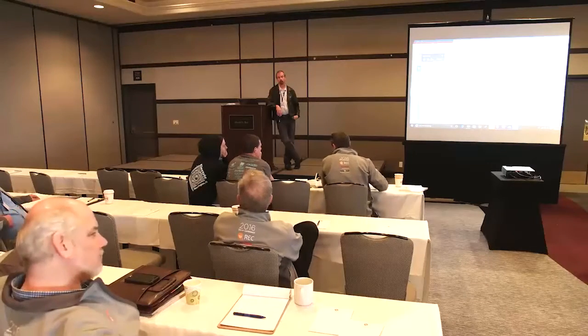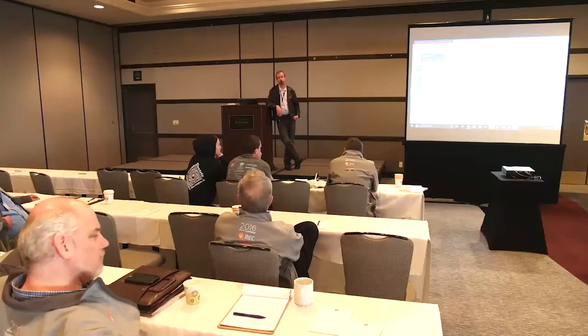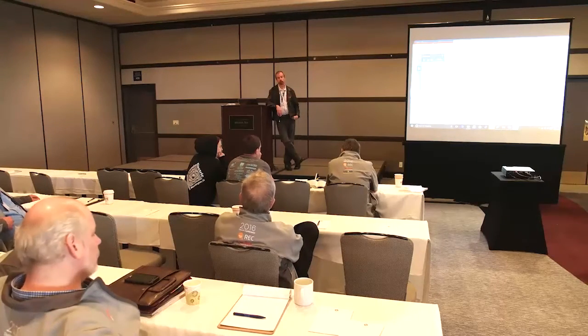The only folks that have really ever even thought about this beyond PV have been lightning protection people, because metal roofs can cause some real problems with lightning protection. So it makes all the sense in the world with a lightning protection system that you're going to run air terminals across the ridge of your roof, that you got to bond to that metal roof. Up in our area, the metal roofs are very, very popular, and they don't seem to be concerned about lightning at all. They're just a plain metal roof. Yeah, and they're over wood.